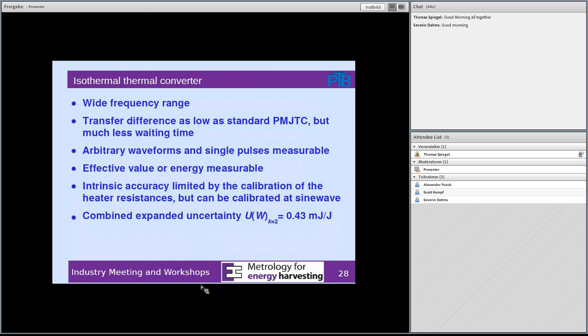So summarizing, I could say isothermal or calculable thermal converters have, contrary to direct sampling, a very wide frequency range up to 1 megahertz. They have transfer differences as low as thermal standards, but much less waiting times. The main advantage is that we can now measure arbitrary waveforms and even single pulses. We can choose whether we would like to measure the effective value, that means an equivalent DC, or if we would like to measure the energy content in a pulse.